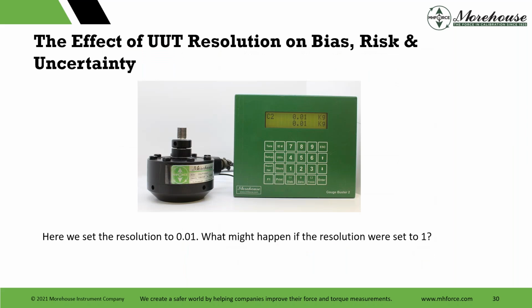I said before the effect of resolution and uncertainty. Here we set the resolution to 0.01. If we set it to 1, what might happen? This is a load cell, a 1,000 kilogram load cell. If we look at a test report, this is an ASTM test report for a 3,000 pound load cell. So if the resolution is high, guess what? We show nothing. And on this report, standard deviation 0.